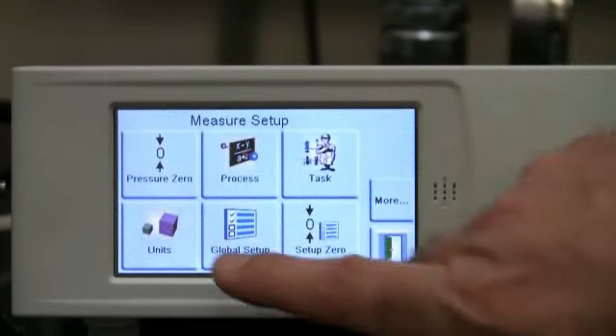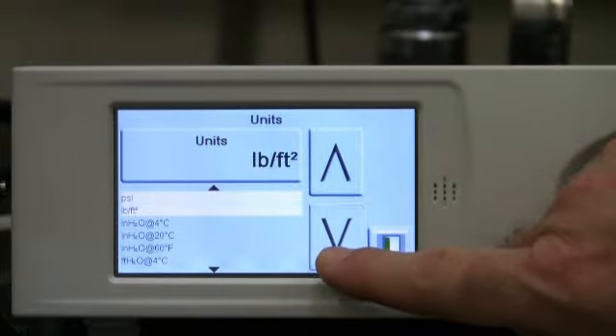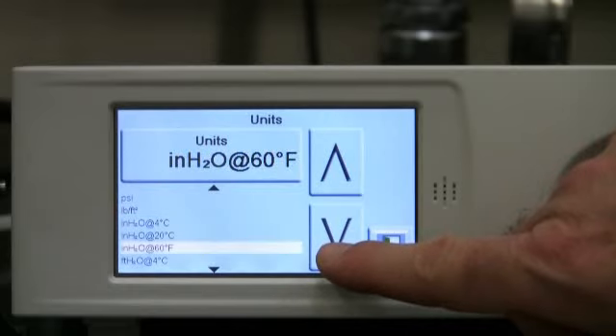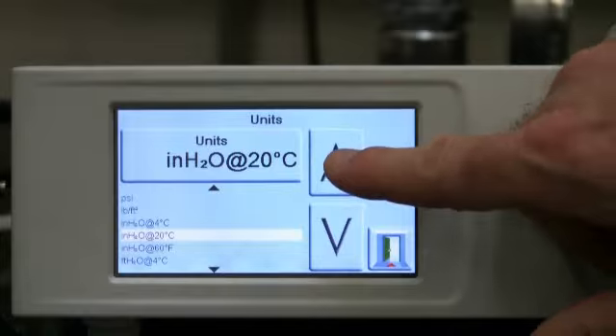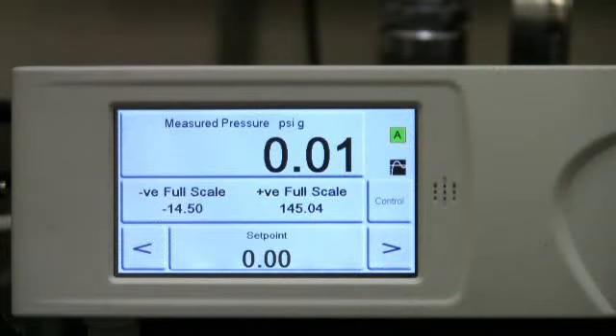Since the DPI 104 is presently displaying units in PSI, we will select PSI on the PACE5000. PACE5000 includes 24 different pressure units to choose from. If the required unit is not included, there are 4 user-defined units that can be created.